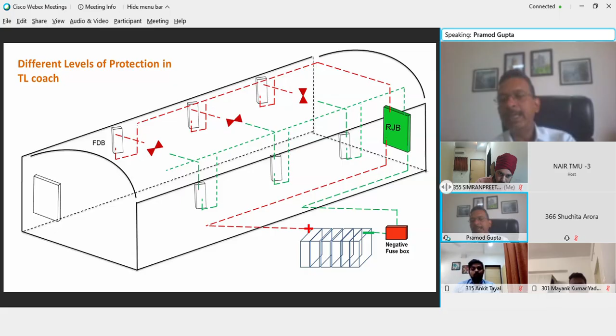We also have junction boxes - two on either side of the coach, with different fuses, each taking care of one major circuit. The entire circuit is divided into two circuits known as L1 and L2. If there is a major fault in one circuit, that circuit becomes out of service, and the associated HRC fuse gives an indication. This is the second level of protection.